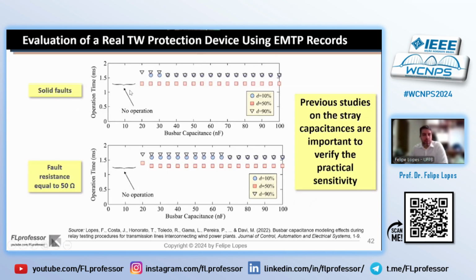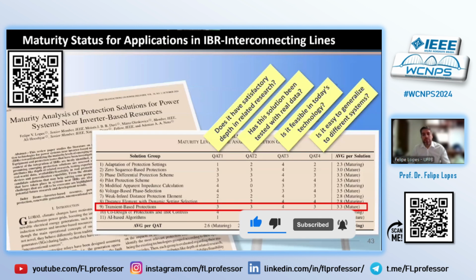We could find this margin of sensitivity here. And this is why we usually say that a previous study on the stray capacitance is important to verify the practical sensitivity. Otherwise, if you have communications, you can monitor the grid side only and just release tripping commands to the IBR side if necessary.